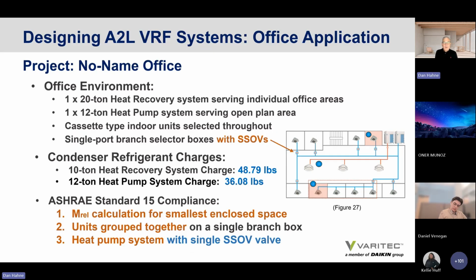And here's an example for an office building using safety shutoff valves at each of the branch selector boxes, serving one fan coil unit each. And we can see by that the condenser refrigerant, total pounds of refrigerant for the condensers used are listed at 48.79 and 36.08. And then to meet standard 15 compliance, the MREL calculation should be for the smallest enclosed space.